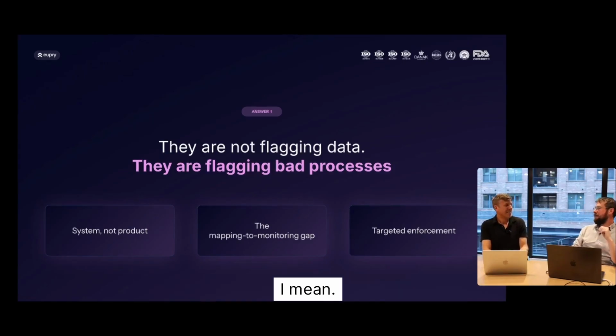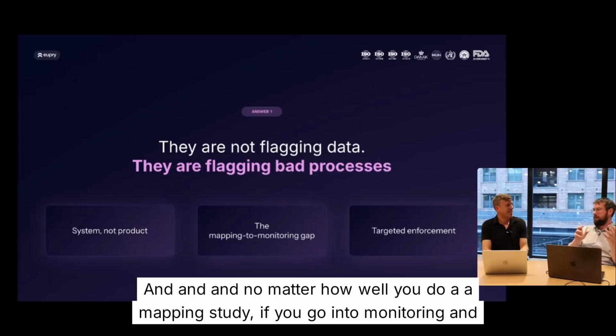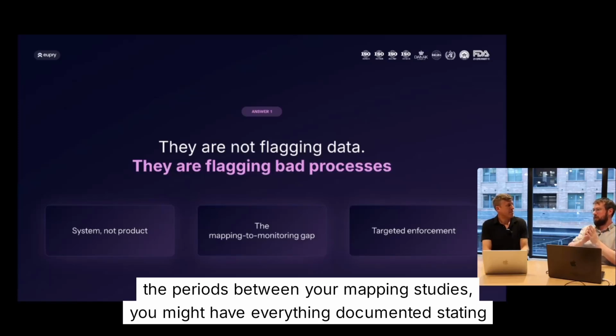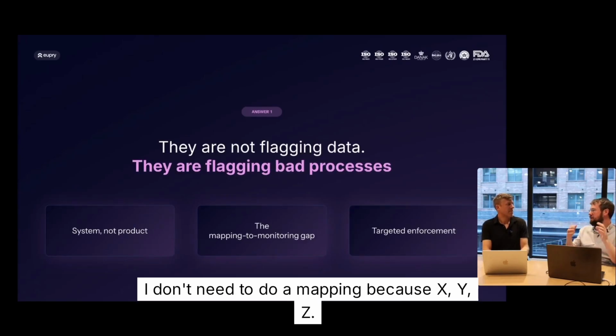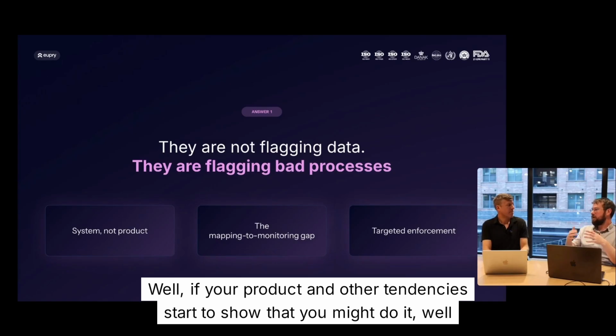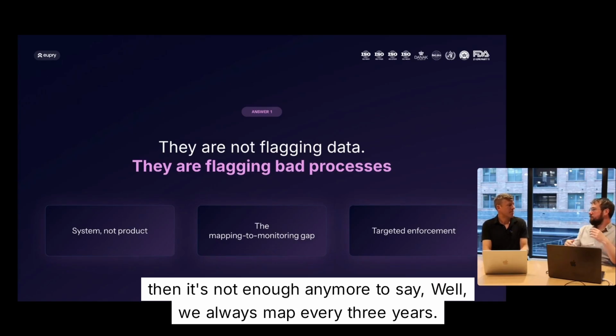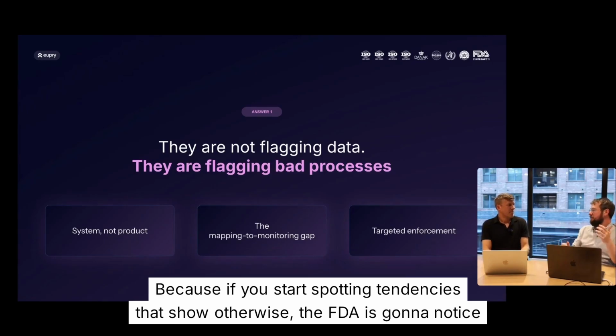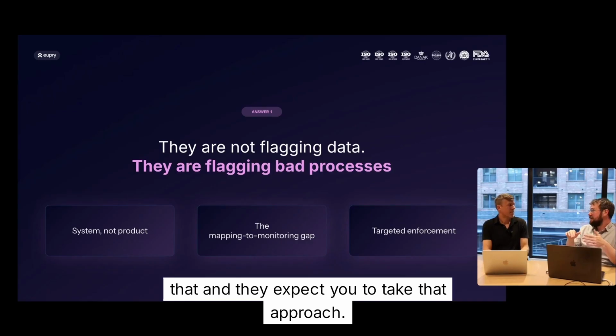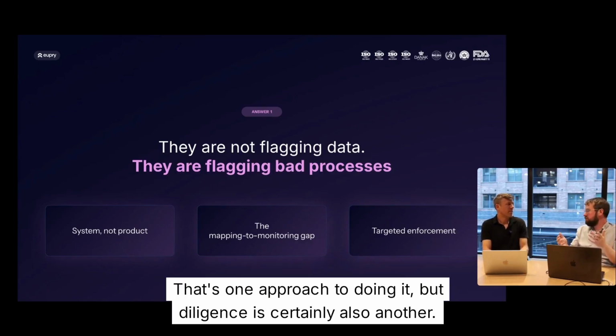Yes. And no matter how well you do a mapping study, if you go into monitoring and the periods between your mapping studies, you might have everything documented stating, I don't need to do a mapping because X, Y, Z. Well, if your product and other tendencies start to show that you might need to, then it's not enough anymore to say, well, we always map every 3 years. Because if you start spotting tendencies that show otherwise, the FDA is going to notice that. And they expect you to take that approach with continuous temperature mapping. That's one approach to doing it, but diligence is certainly also another.